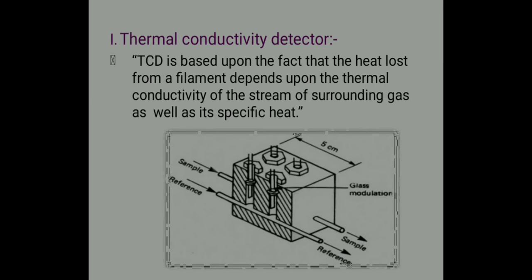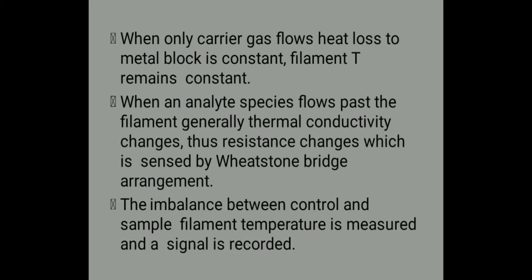Now this TCD is based on the fact that the heat loss from a filament depends upon the thermal conductivity of the stream of surrounding gas as well as its specific heat. When only the carrier gas flows, heat loss to the metal block is constant and the filament temperature remains constant.